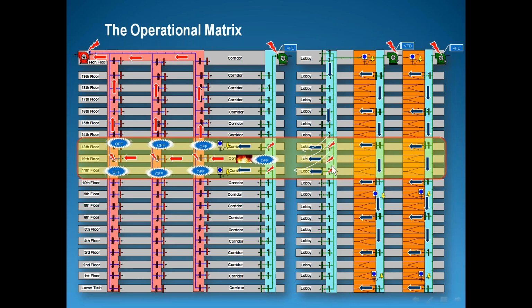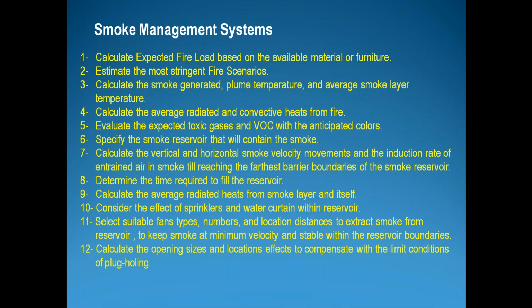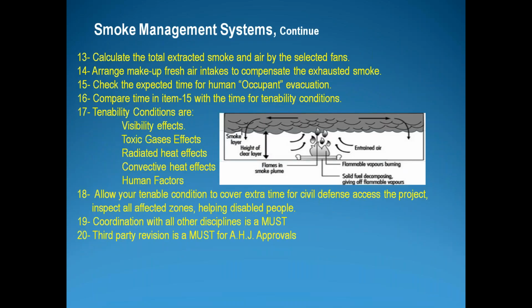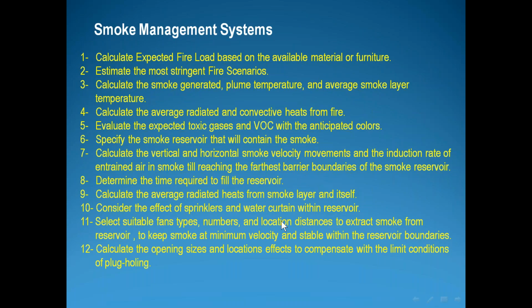Then here the control with the other dampers. Here we have the damper of the shaft and pressurized the lobby of the elevators. So you will find here about 20 items. Yes, 20 items for the precautions that we have to consider when we design the smoke management system. These 20 items shall move us to the beginning of this lecture.